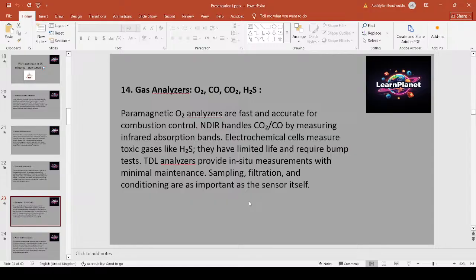Paramagnetic O2 analyzers are fast and accurate for combustion control. NDIR handles CO2 and CO by measuring infrared absorption bands. Electrochemical cells measure toxic gases like H2S. They have limited life and require bump tests. TDL analyzers provide in-situ measurements with minimal maintenance. Sampling, filtration, and conditioning are as important as the sensor itself.